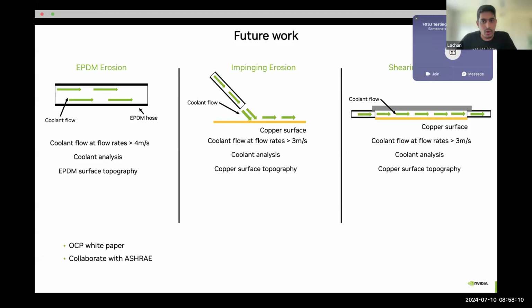Along with that, we are looking into copper erosion as well, where the first one would be impinging erosion. What would happen to a copper surface when the coolant is directly impinging on the surface at a 90 degree angle, for flow rates higher than 3 meters per second. We'll be looking into the copper surface topography and also at coolant analysis to see the copper content and other parameters vary from period to period. And the third case would be the shearing erosion, where the coolant will flow parallel to the copper surface, like you see in this schematic. The coolant flow rates we are right now considering going over 3 meters per second. It would mostly depend upon the maximum capacity of the pumps. So that is our current work.